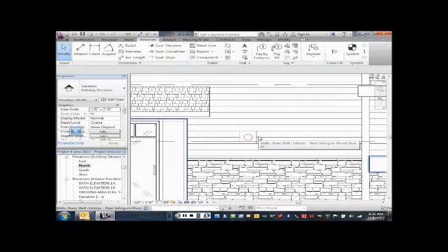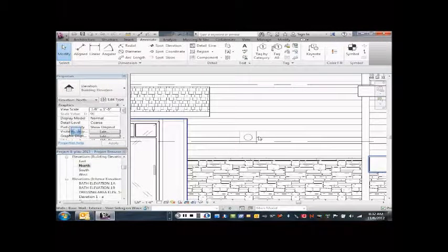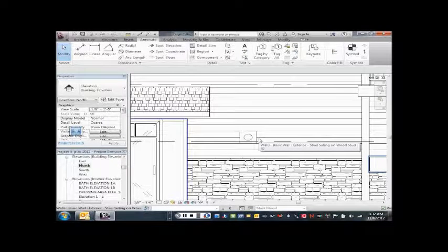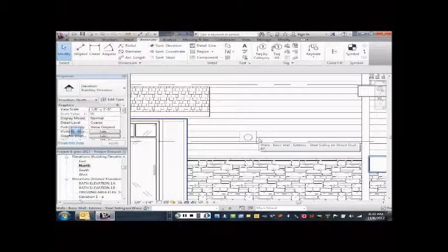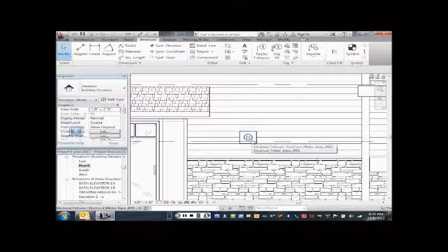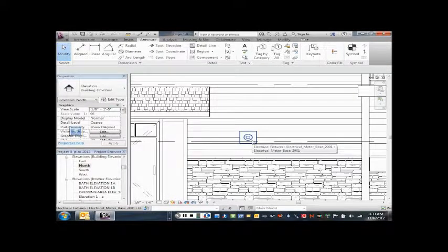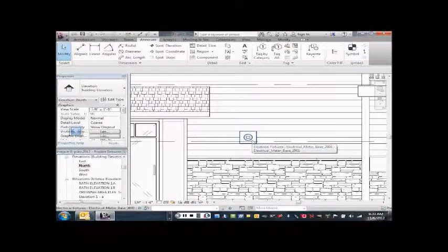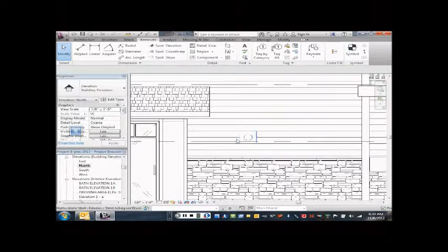Now, in this building, I want to meter the commons area of the building separate of each of the units. So each tenant that moves in will pay their own electric bill. So I'd have to have a meter for every tenant in the building. That make sense? Okay, so I need a meter for the house, which is going to be the meter for the laundry room, the mechanical room, the lights in the corridor, things like that, right? So that's what that meter is going to be for, and I need 8 other ones.